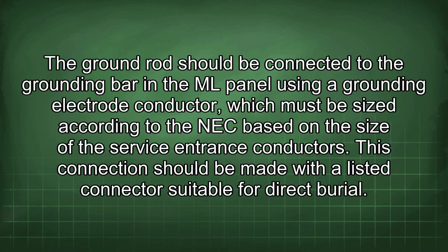The ground rod should be connected to the grounding bar in the ML panel using a grounding electrode conductor, which must be sized according to the NEC based on the size of the service entrance conductors. This connection should be made with a listed connector suitable for direct burial.